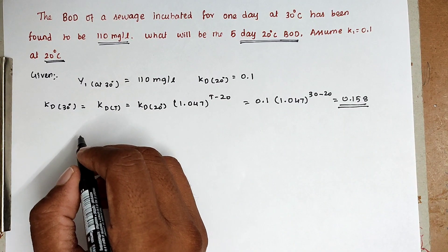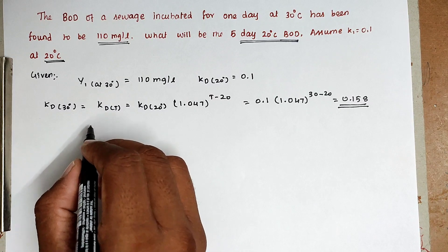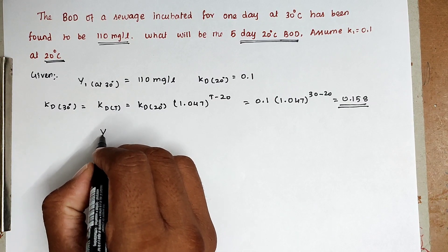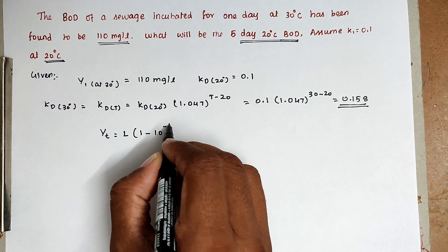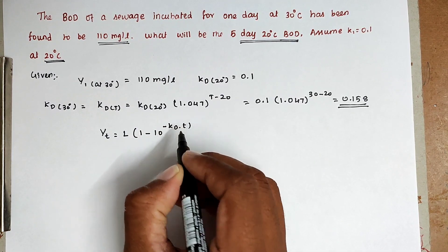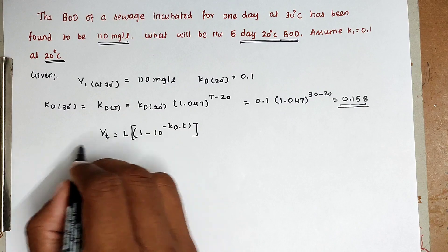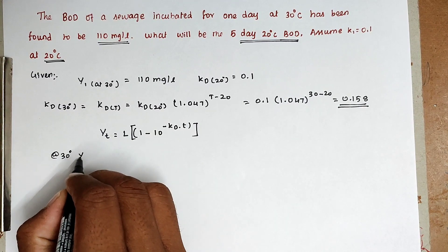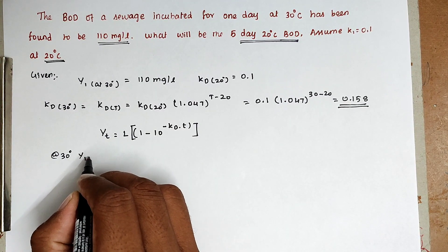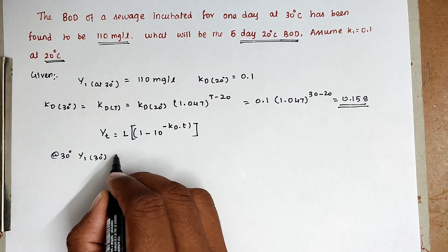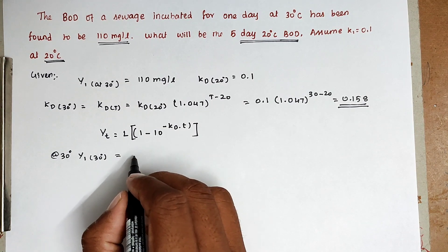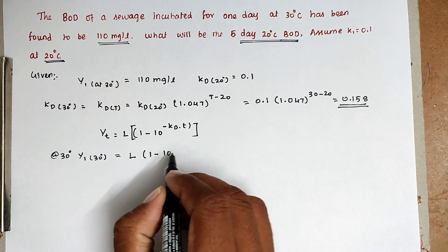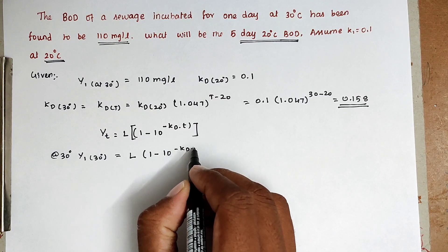Now we can find the ultimate BOD, L, using the formula: Y_T = L × (1 − 10^(−KD × T)). We know the 1-day BOD at 30 degree Celsius, so we can use this formula: Y at 1 day, 30 degree Celsius = L × (1 − 10^(−KD × T)).